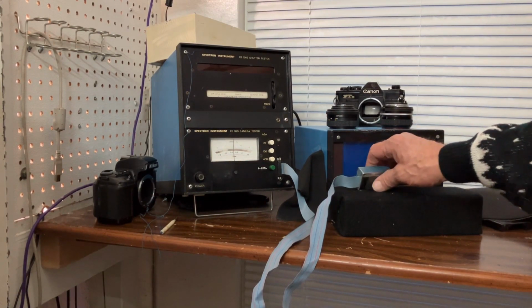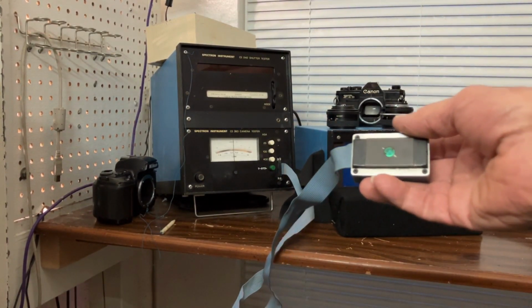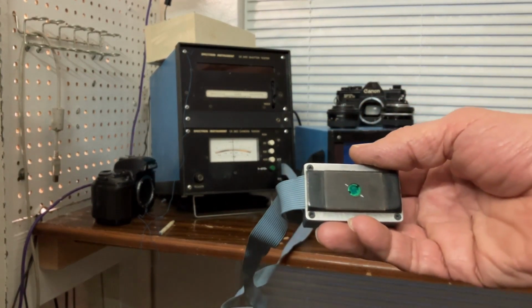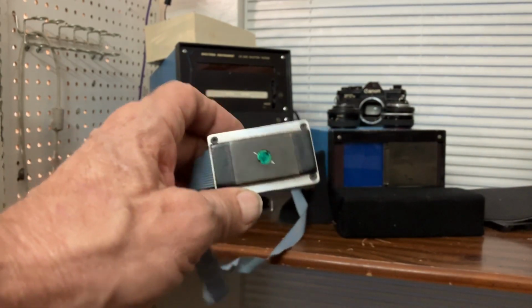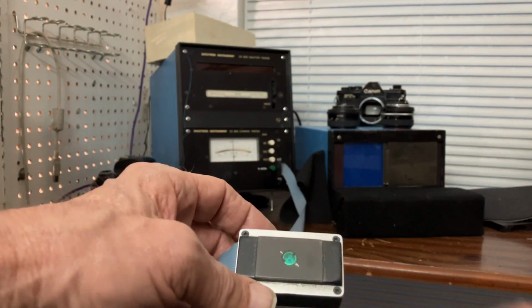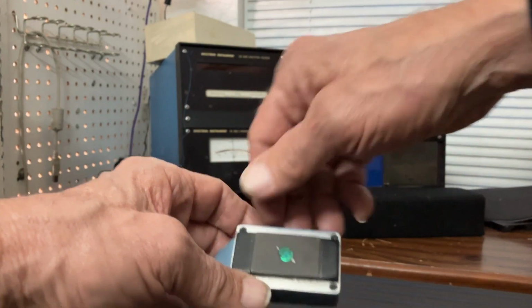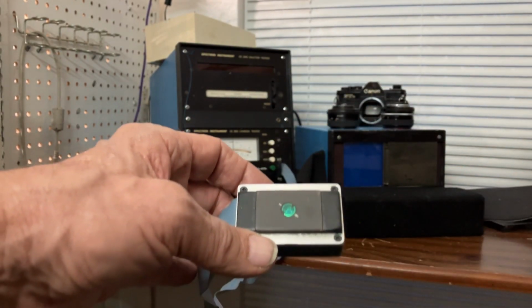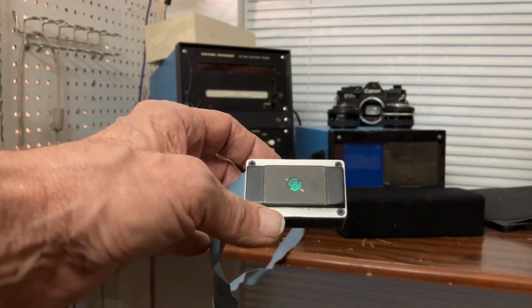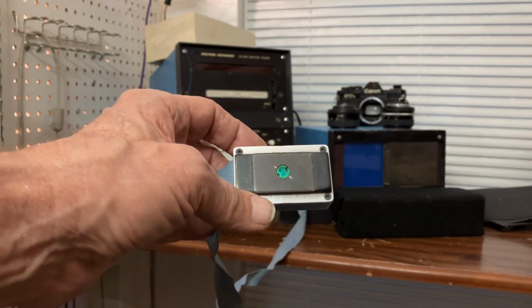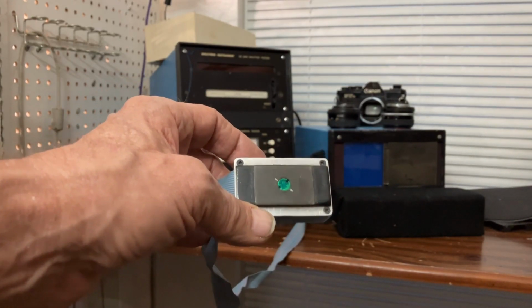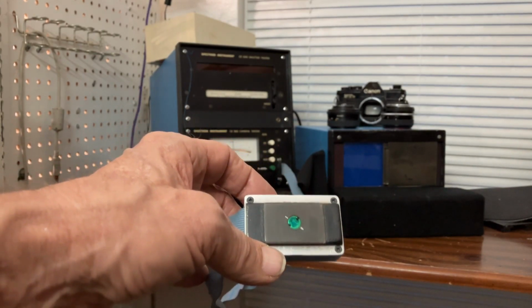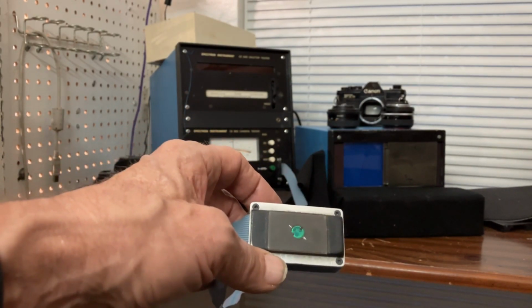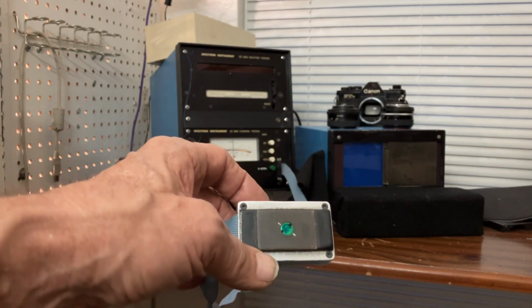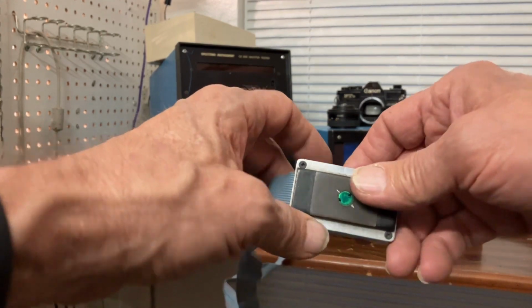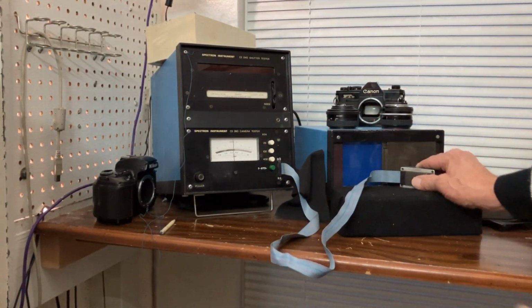The most important thing on the tester is the probe. In another video I do talk about the probe, but since we're just doing the tester, I'll go ahead and talk about it again. It's a 3-sensor probe. There's a sensor here to check the first opening curtain, and a sensor there to test the closing curtain. Then the center sensor, that's kind of a bluish green, is an exposure sensor that also tests the shutter speed. If you're doing a leaf shutter, we have a format sensor for that, or you can use this over the light source and check pretty much any type of shutter.